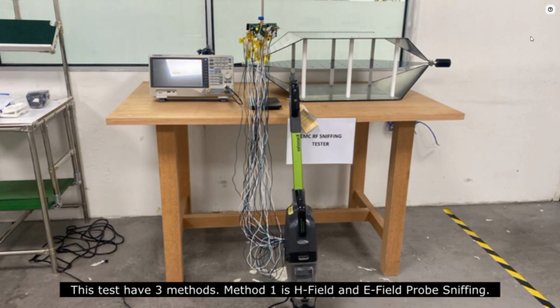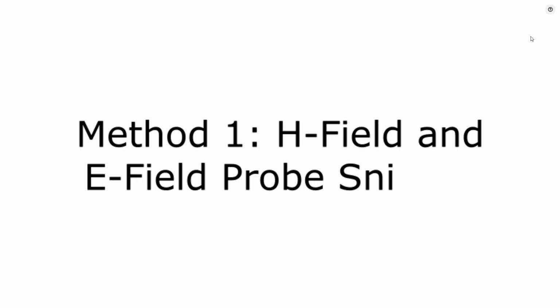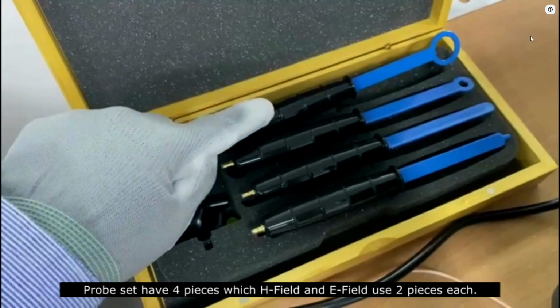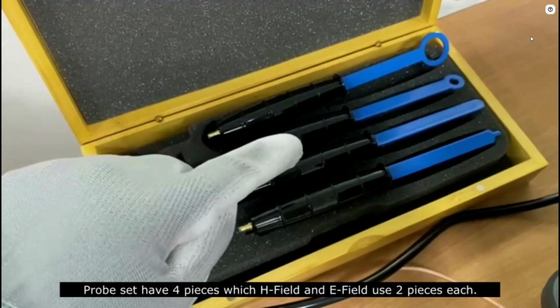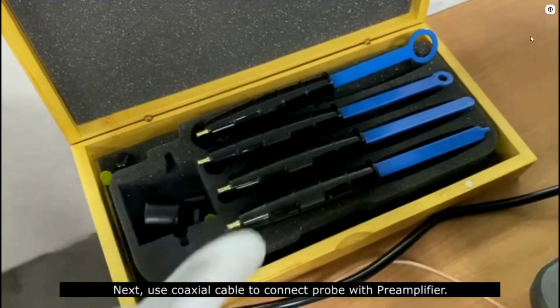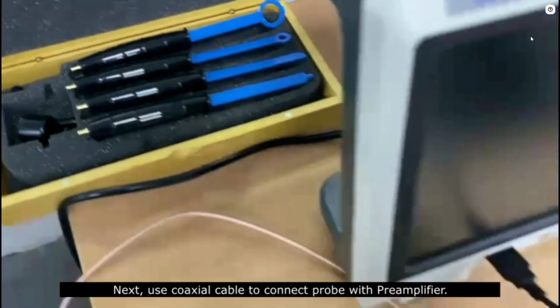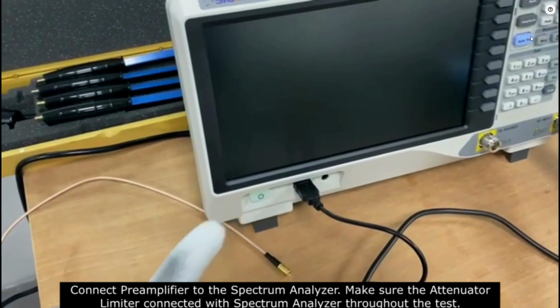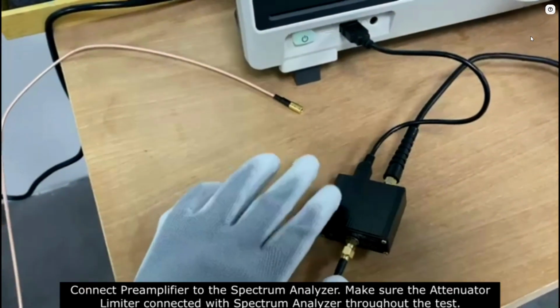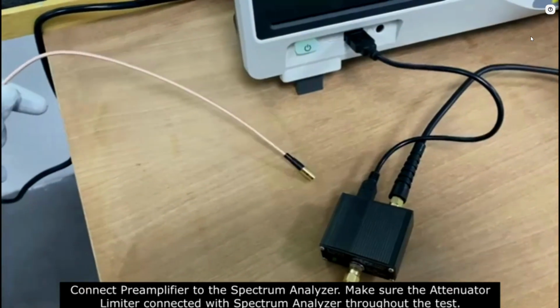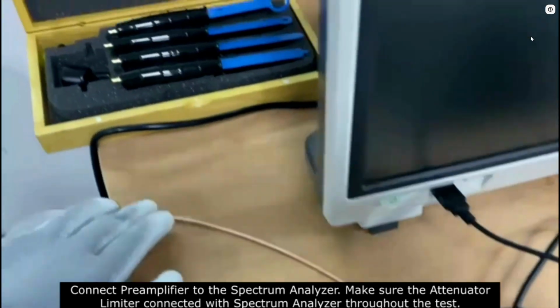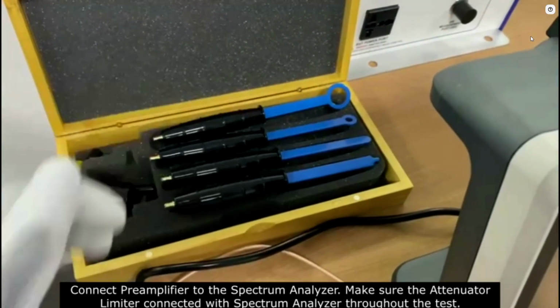Method 1 is H-field and E-field probe sniffing. The probe set has 4 pieces, with H-field and E-field using 2 pieces each. Next, use coaxial cable to connect probe with preamplifier. Connect preamplifier to the spectrum analyzer. Make sure the attenuator limiter is connected with the spectrum analyzer throughout the test.